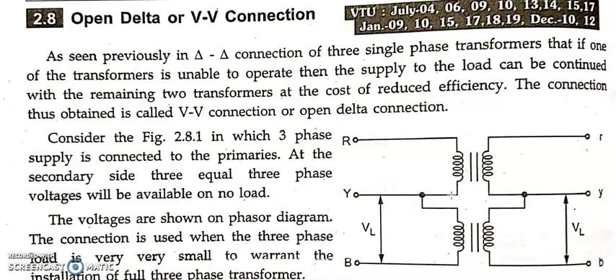Say out of 3 transformers, if you are using only 2 transformers, then in layman's language it will be 2 by 3. Yes or not? Means you are using 2 out of 3 transformers. 2 by 3 is nothing but how much? It is around 66.67. Means you are using 66.67% of the kVA of the total transformers. But in actual it is not so. It is not 66.67, it is something else. Let us see why in the coming derivation.